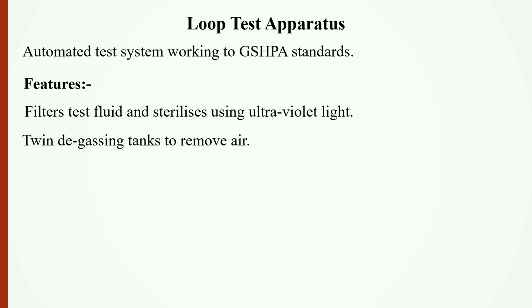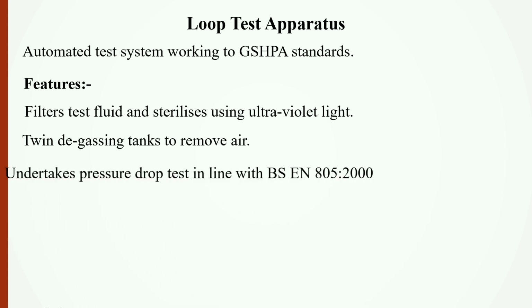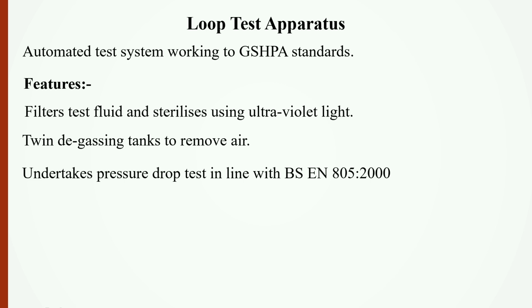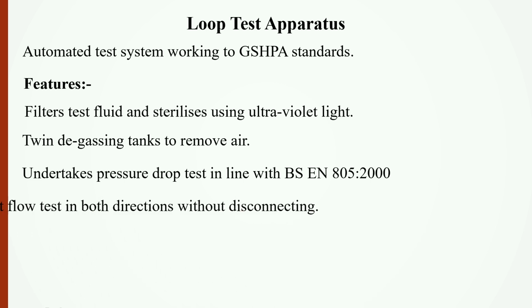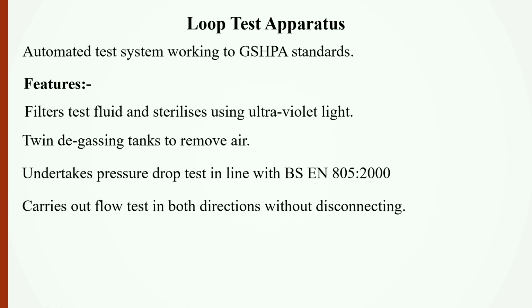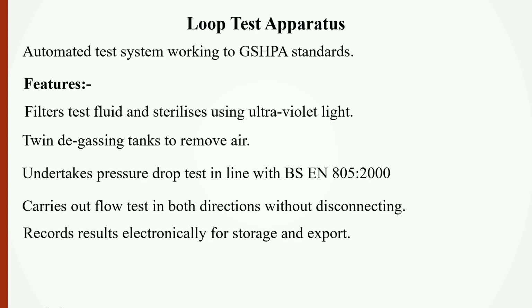We remove the air by having a twin degassing tank to remove that. The unit will then do the pressure drop test in accordance with BS EN 805. It will then test the flow in both directions without disconnecting. All the results that we take are electronic. They're recorded and stored for export.